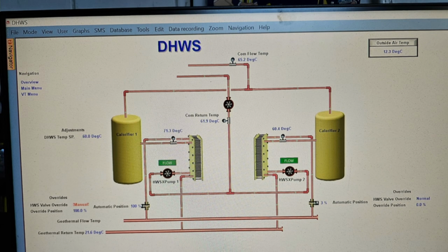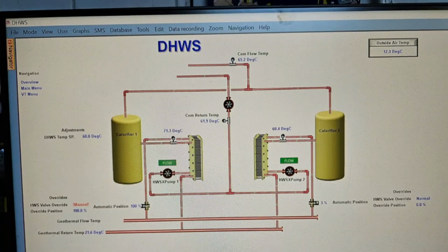That's all looking good. We looked at it and said, hang on a second, where's that 21.6 degrees coming from at the bottom there? We went around, we found the sensor that was giving us that reading, and it was hanging in open air. It wasn't even connected to the pipe. So someone in all this time, and the BMS system's looking at this saying, well, that's the temperature, it must be correct. But only by looking at it and studying it in some detail did we find that there were problems. But this is a typical system.